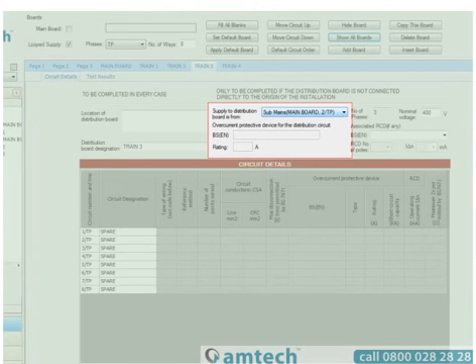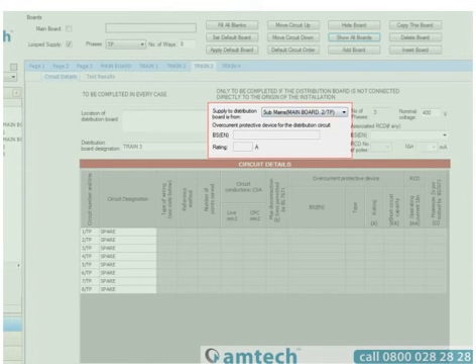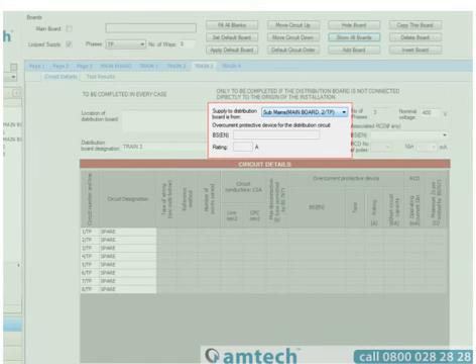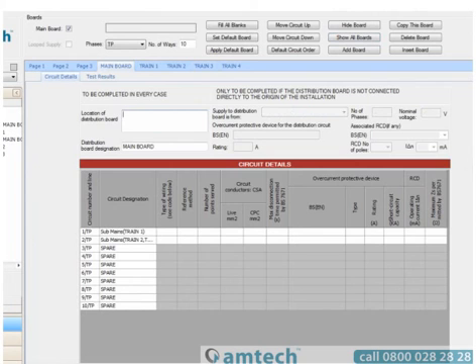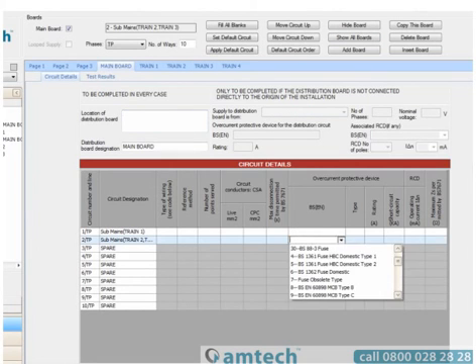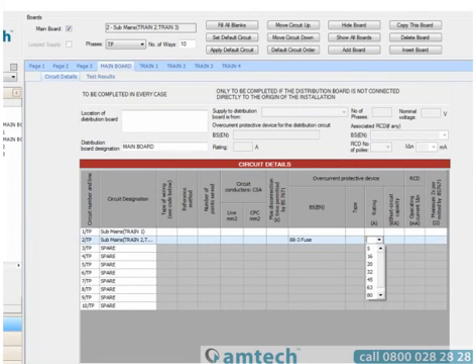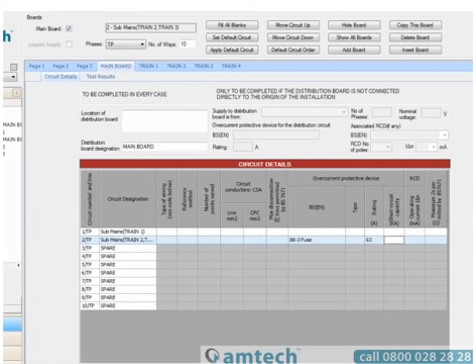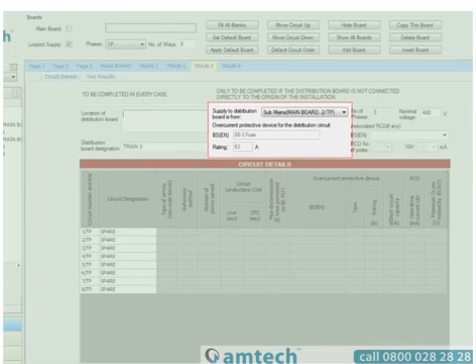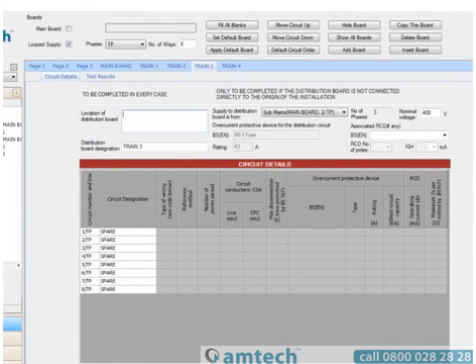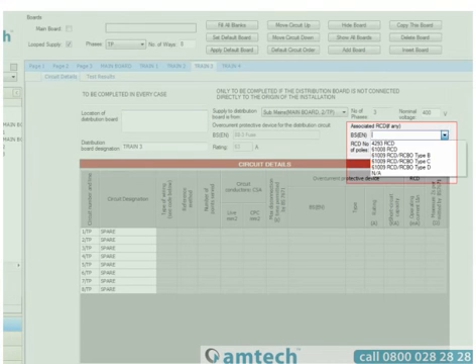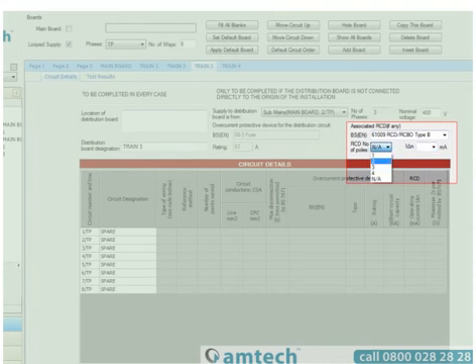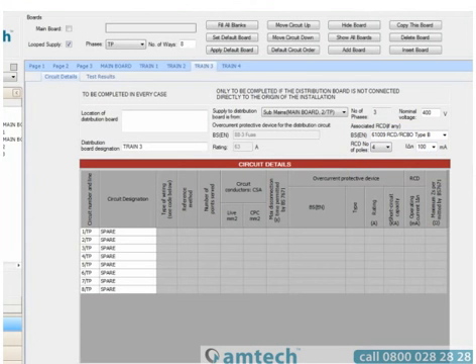Data is automatically completed in this section here by the Submain. In this case, this board is connected to Submain's Main Board 2TP. If I return to Main Board and go to 2TP, if I complete the Overcurrent Protective Device values and its rating, and then return to Train 3, we can see that the values have been transposed into this location. Should you have any form of RCD protection for that Submain's, it can be entered here by selecting it from the dropdown, and then the relevant values entered. And that's the basics of entering boards and modelling their values. Thank you for watching.